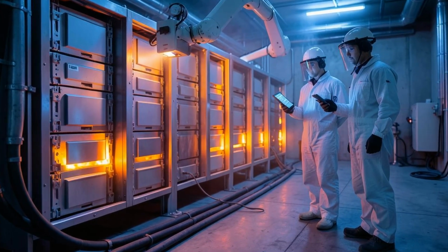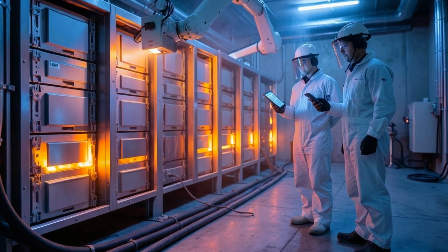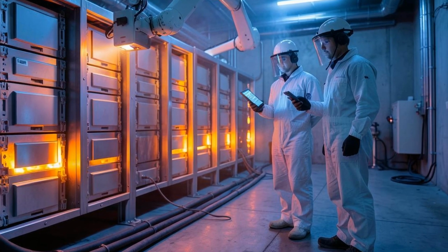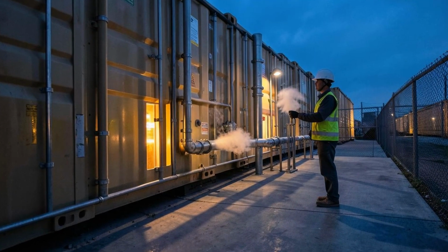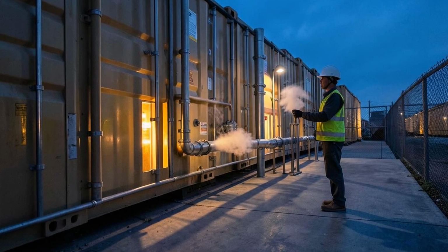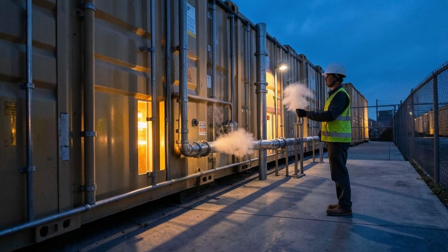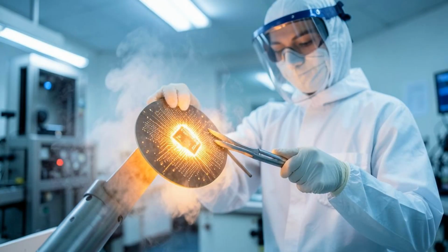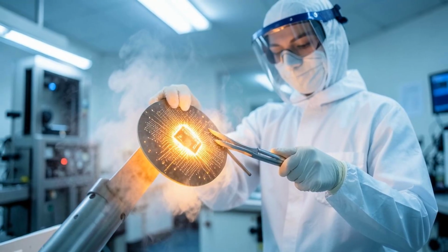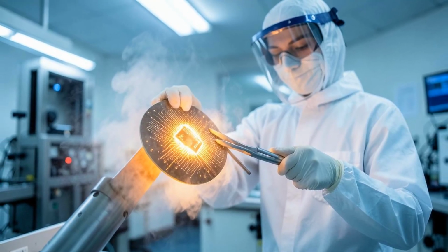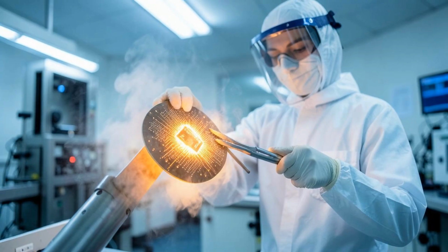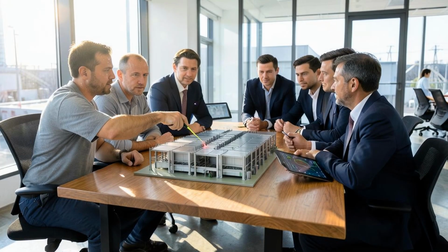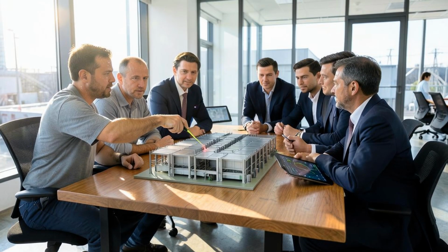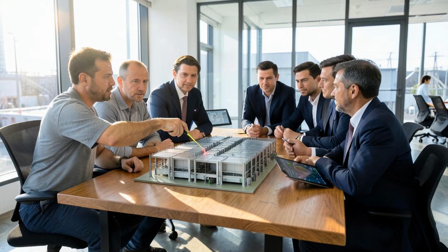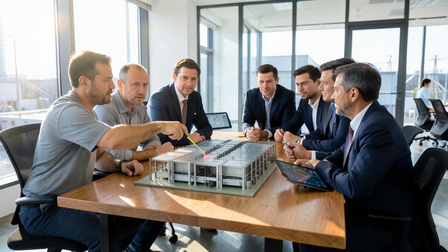The result is immediate thermal throttling. The processors detect the excessive heat and automatically reduce their clock speeds to prevent melting. This means the theoretical performance metrics, the tera operations per second that the marketing materials tout, become completely unachievable. The hardware becomes a brick that is too hot to touch, not a supercomputer. The physics of thermodynamics dictates that you cannot contain that much energy density in a small, uninsulated space without active liquid cooling.